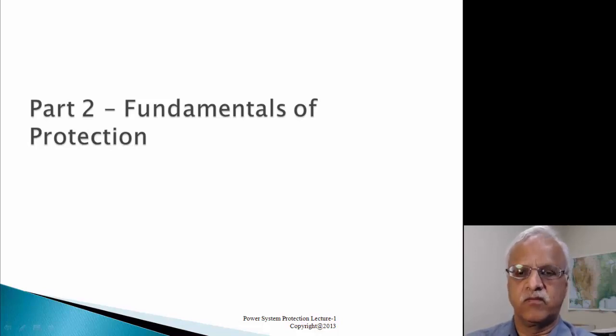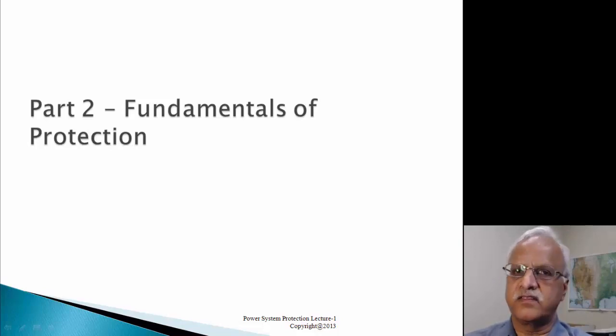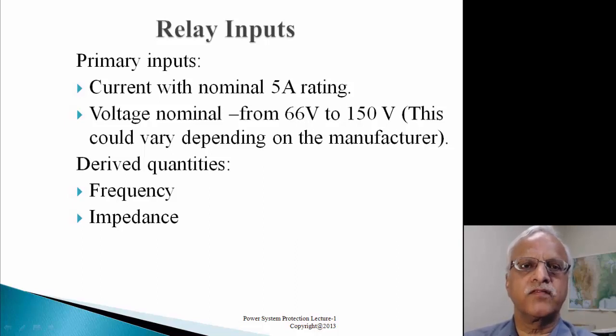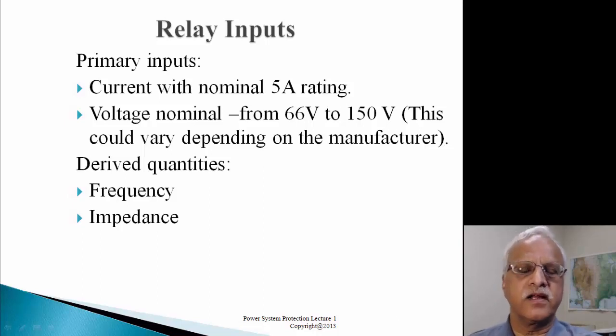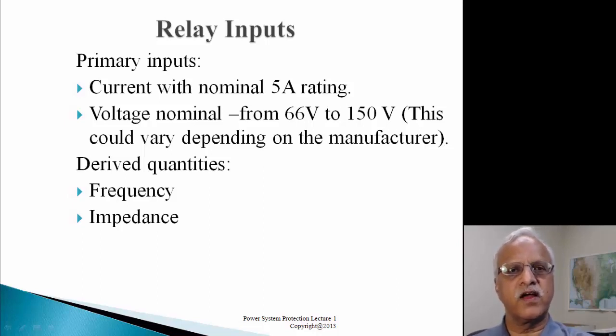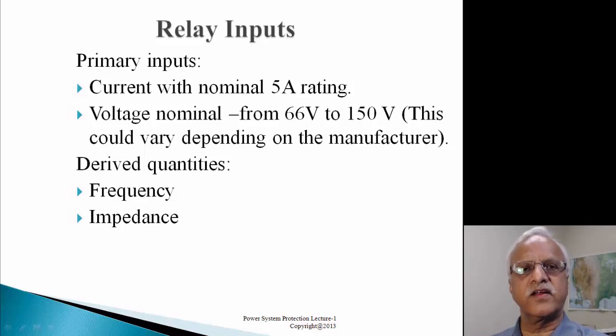Relays monitor the system for healthiness, and if they find any abnormality or short circuit in the system or any equipment, they isolate that particular equipment as soon as possible. The relay inputs we talked about were currents with a nominal rating of 5 amperes. If the primary current is 2000 amperes and we use current transformers, we step down these 2000 amps to 5 amps on the secondary side, connected to the relay as input. Similarly, we have a voltage input where we step down primary voltages to secondary manageable values.